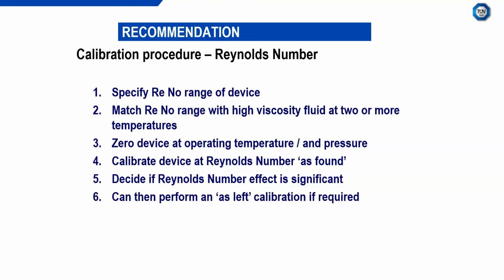So again, remember, it's going to be that linear effect, but you can adjust. You can pull the results up or down as well. So you're still going to have the linear effect, but you're going to basically be changing the offset when you do that as found, as left calibration.